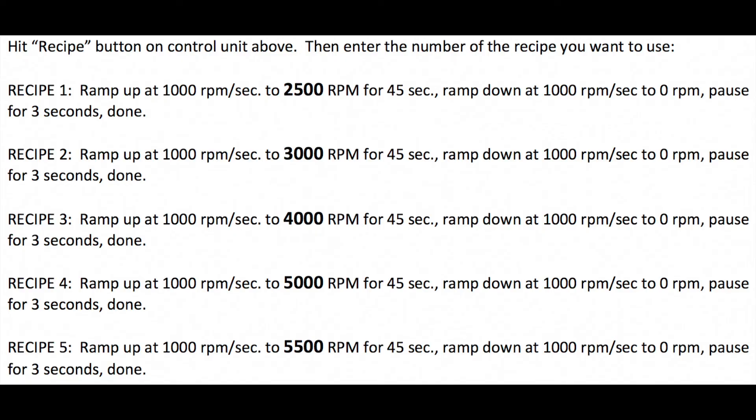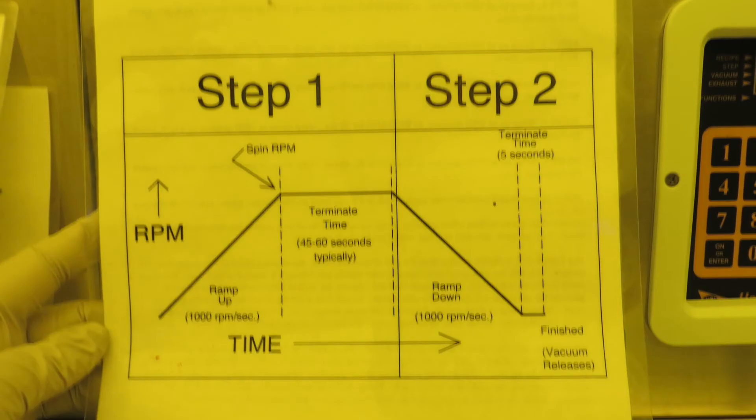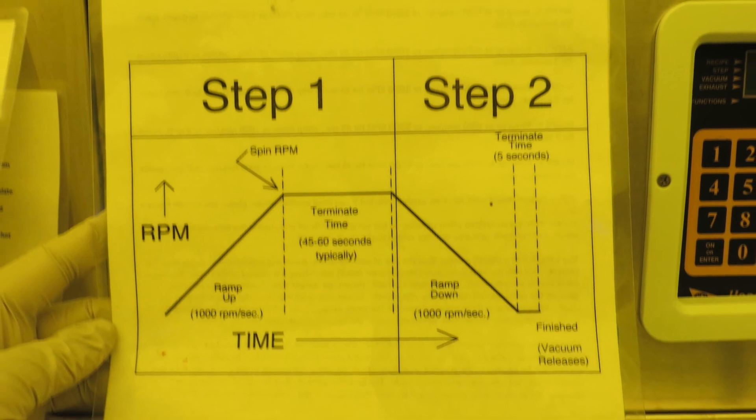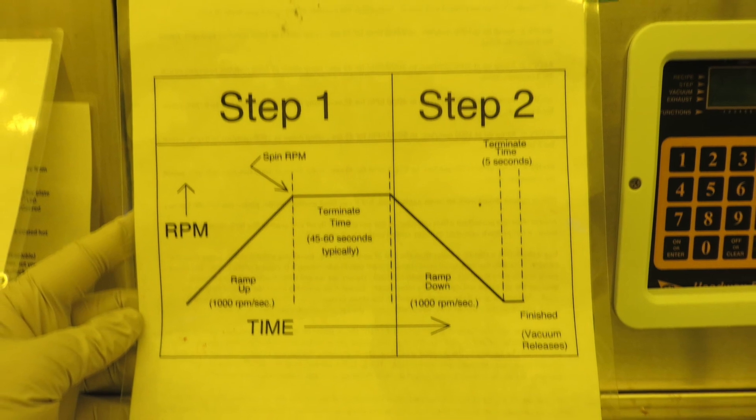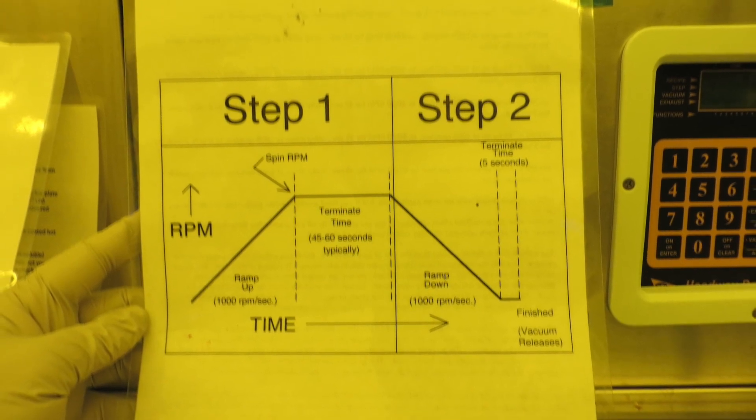Now I'll talk about programming custom recipes and also how to verify that the standard recipes haven't been changed accidentally. All of the standard recipes have just two steps. Even most of the custom recipes have only two steps, but it is also possible to make a custom recipe with up to nine steps.